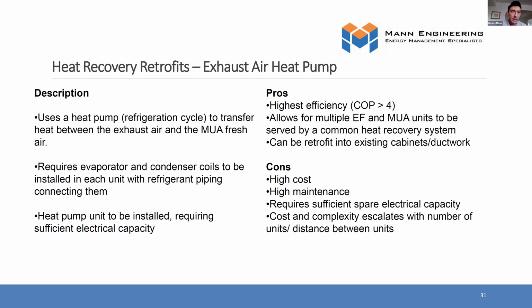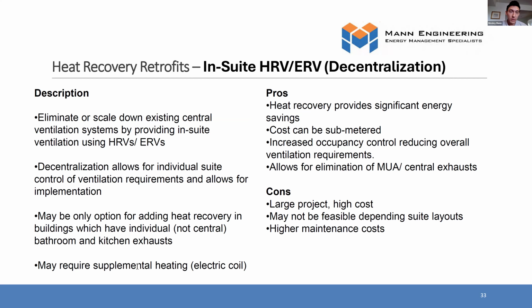The main downside is obviously cost, and it's another piece of equipment you have to maintain. It's another heat pump that you have to maintain, and it relies on having sufficient electrical capacity. Same goes with any heat pump retrofit. You always have to look at whether there is enough electrical capacity on the roof or wherever you're installing it to support that heat pump, because if we have to do any electrical upgrades, that adds significant cost.